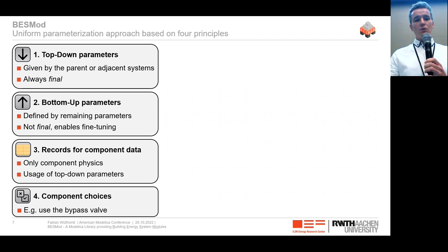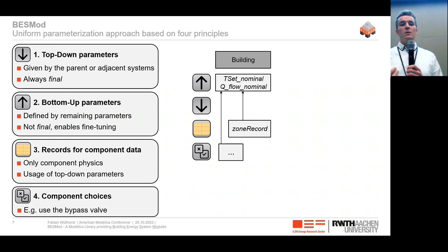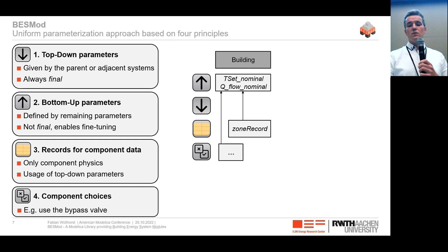If we have a subsystem containing the building envelope, we can use the record data of the building physics and the bottom-up parameter of the nominal room temperature to calculate, via a set equation, the nominal heat flow rate. This nominal heat flow rate is then used as a top-down parameter in other systems, for example the radiator system, where using it along with other record data we can calculate the nominal mass flow rate, nominal pressure losses, and so forth.